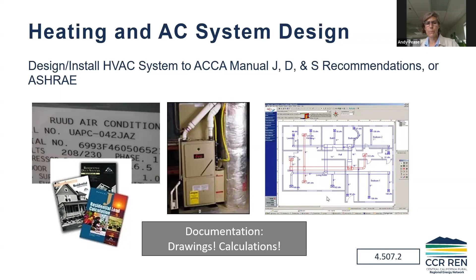It's trying to counter the idea that a 3-bedroom house just needs this size equipment. Oversized equipment doesn't perform as well, and undersized equipment may not provide levels of thermal comfort that are safe. So it's important to get these right sized. There are different programs that will generate this duct layout kind of system, so make sure that you get the drawings and the calculations.